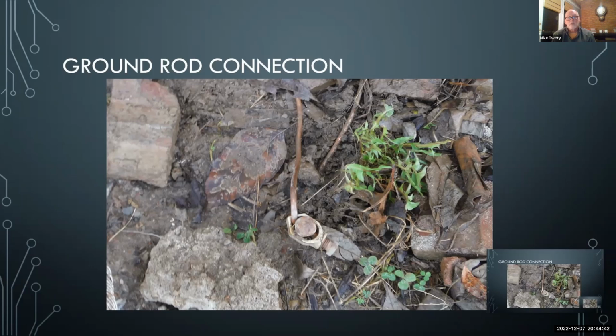These are not allowed for double taps. You can run more than one conductor to that rod, but it requires another acorn clamp or suitable clamp for the other conductor. That's a mistake a lot of electricians make, and they fail inspections. They pay another, whatever the fee is, $40, $50 to go back out there and put another little $5 acorn clamp on there that they didn't do. They'll fail you on that if you don't do that.